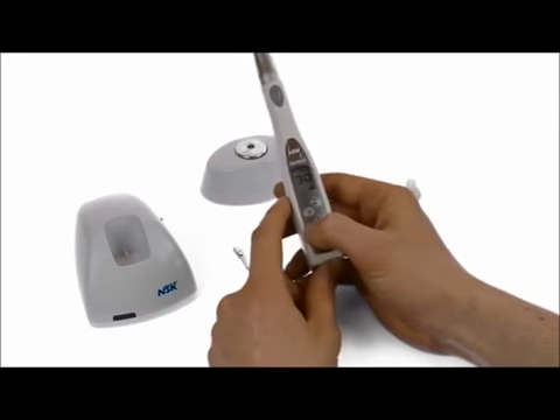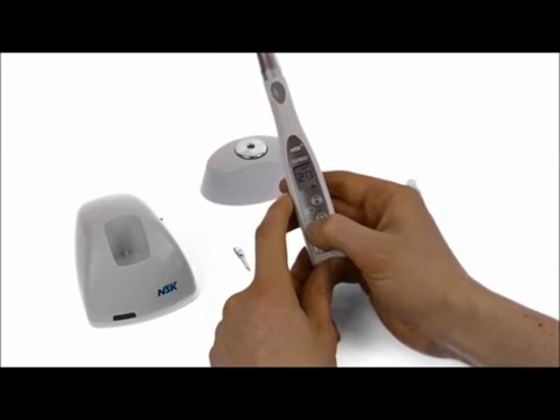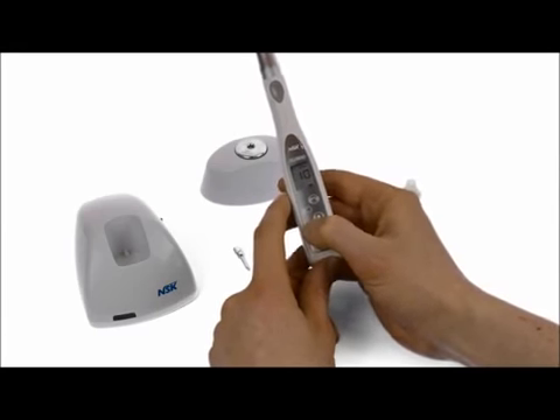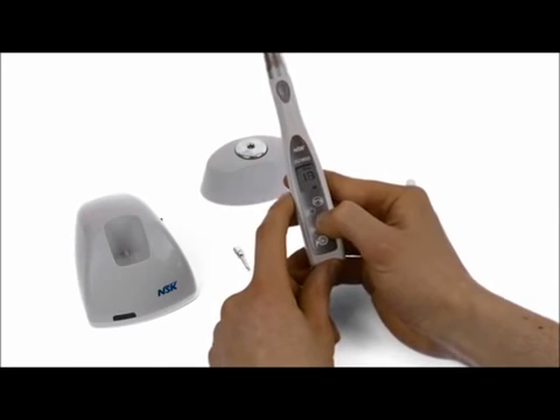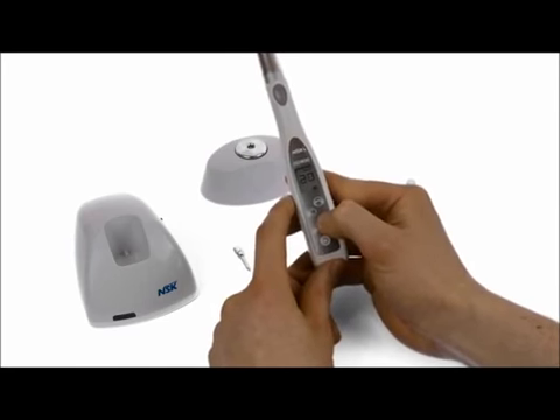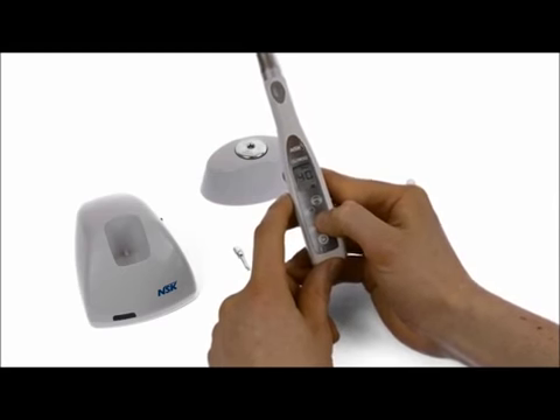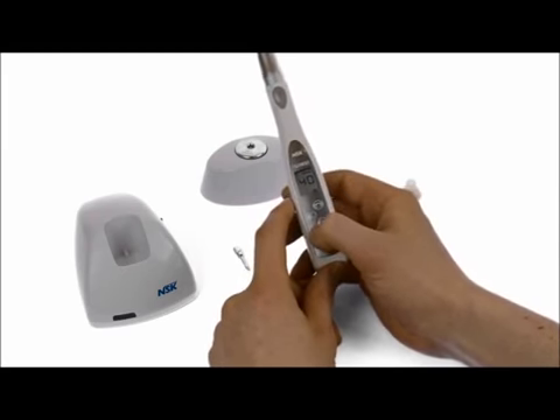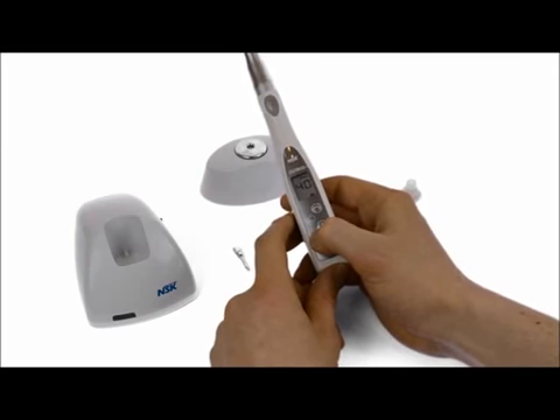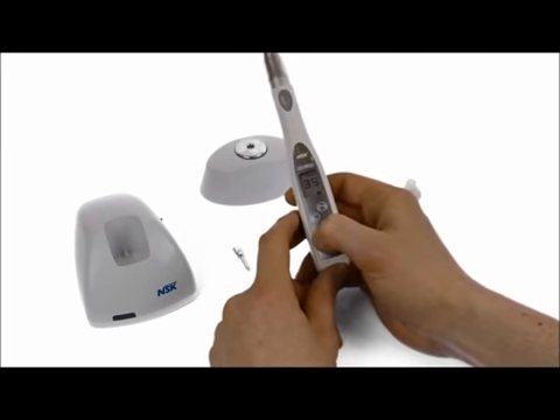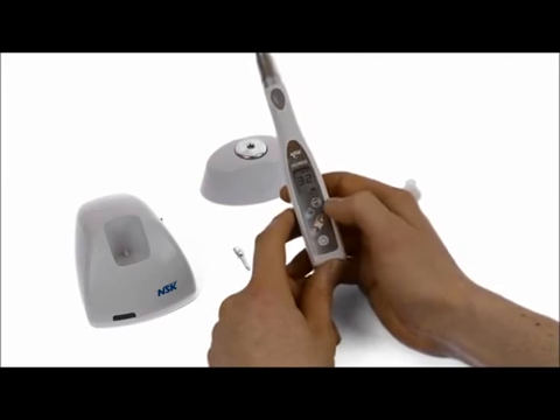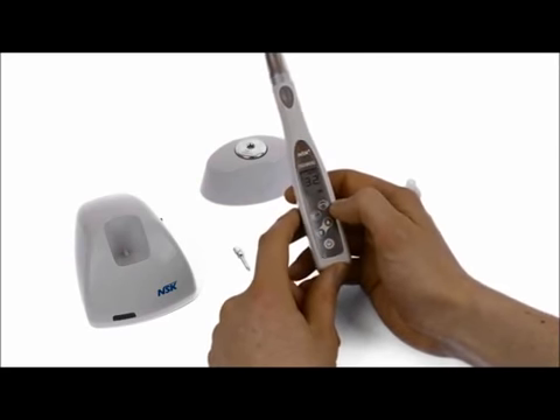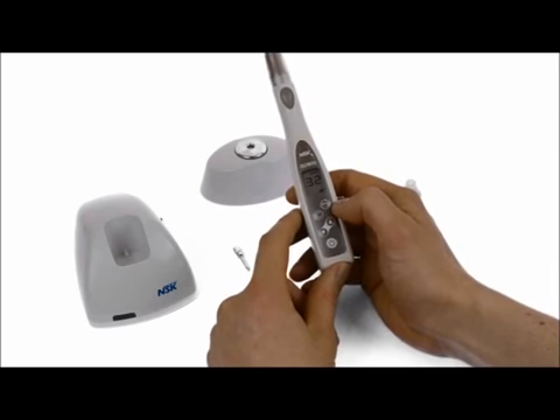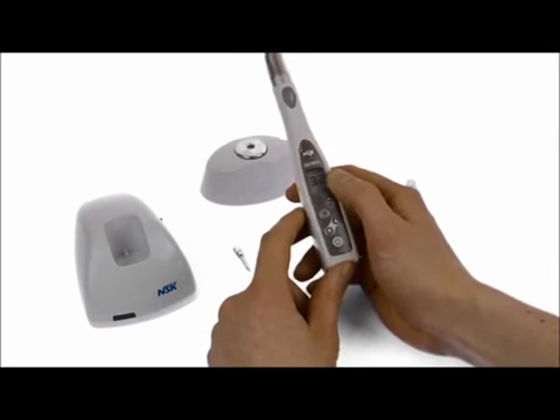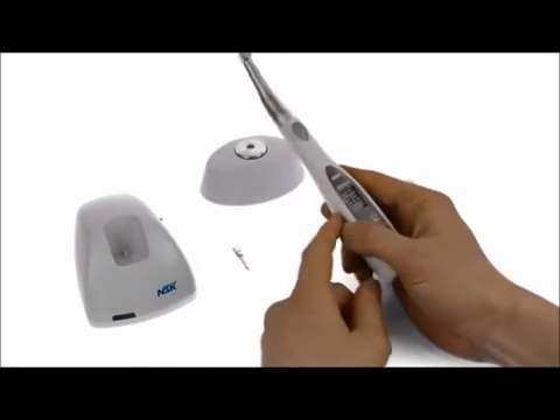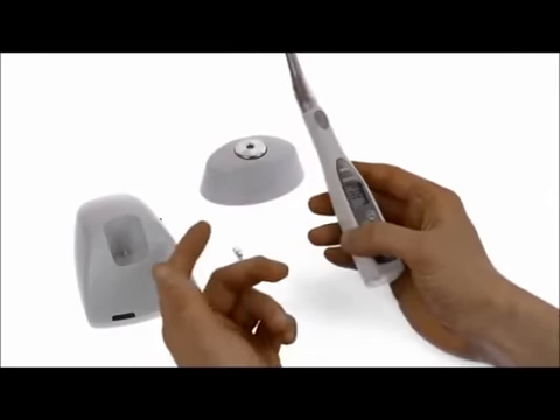Now the torque value can be scaled in single units all the way from 10 Newton centimeters up to 40 Newton centimeters. So this can be set, obviously, as you know, all the different implant systems have their various torque values from 10 to 32 Newton centimeters, so it really depends on the system, but this can very accurately determine what torque value you're applying to that screw. So to make sure that the torque value on the display is exactly what you are receiving from the head of the handpiece, it comes with a calibration device.